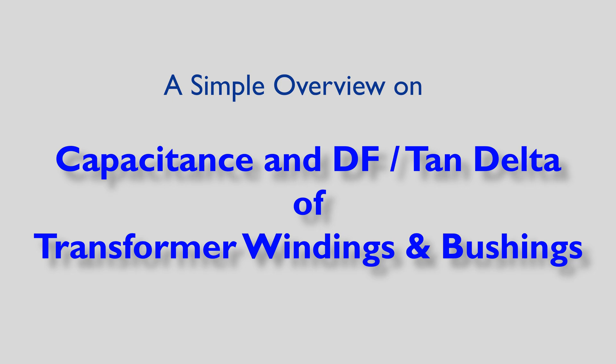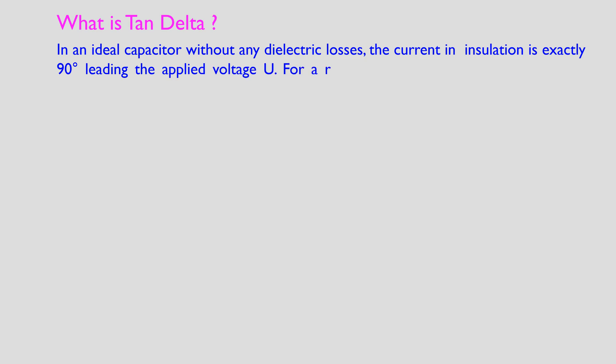What is tan delta? In an ideal capacitor without any dielectric losses, the current in insulation is exactly 90 degrees leading the applied voltage U. For a real insulation with dielectric losses, this angle is less than 90 degrees. Then angle delta is equal to 90 degrees minus phi.